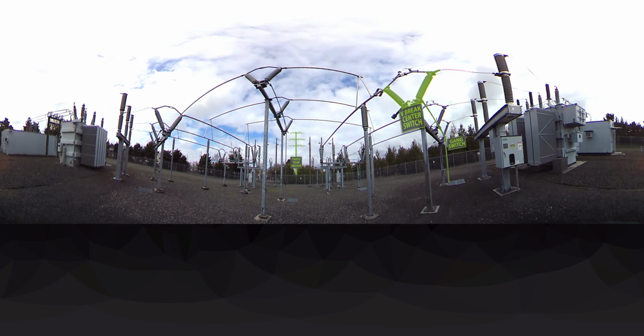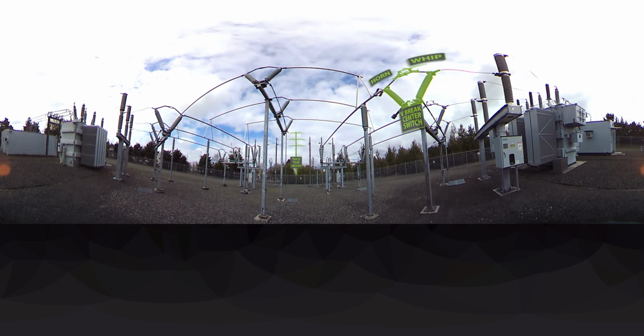The operator would be standing on the adjacent switch mat for safety to manually operate the gang switch. If you look closely at the top of these V-break center switches, you will see what's called a whip and horn. High-speed arcing horns and whips are equipment added to disconnect switches to allow them to interrupt small amounts of charging or magnetizing current.